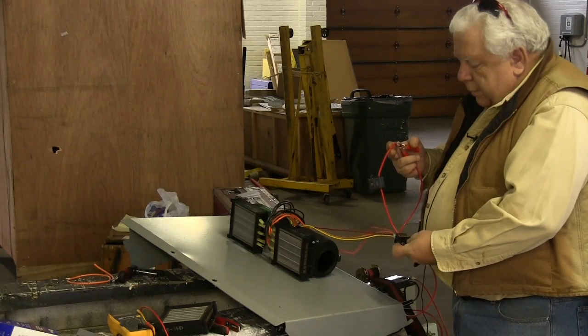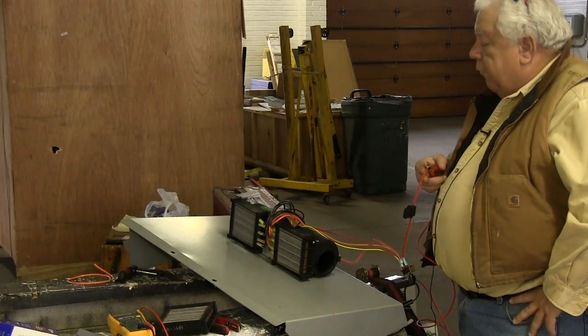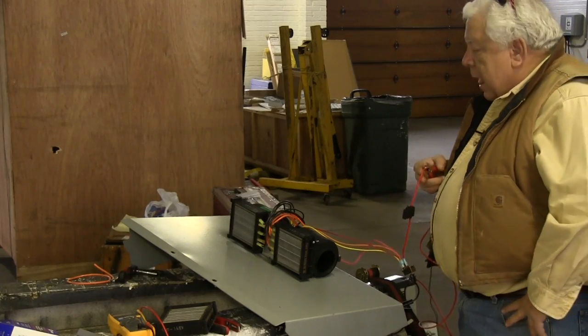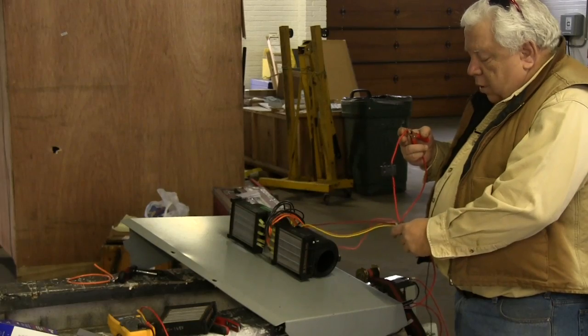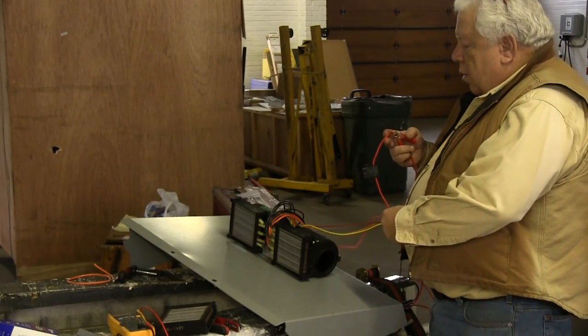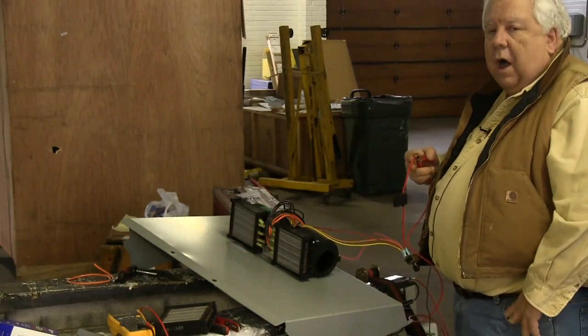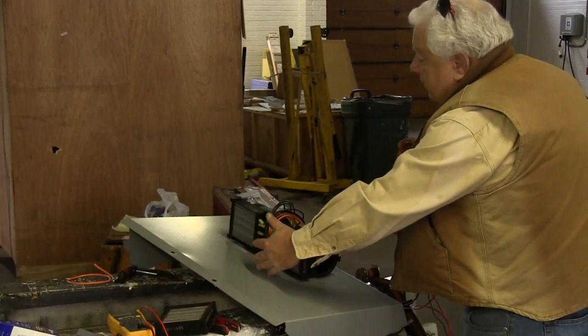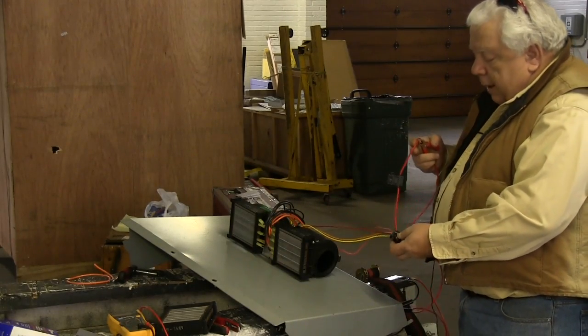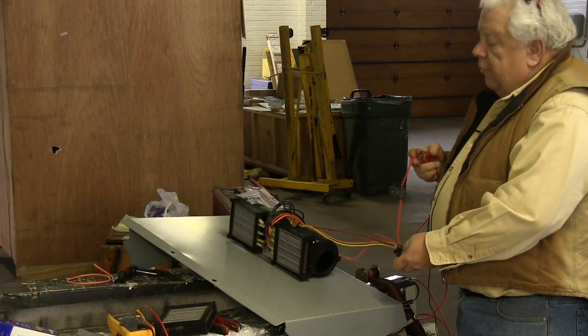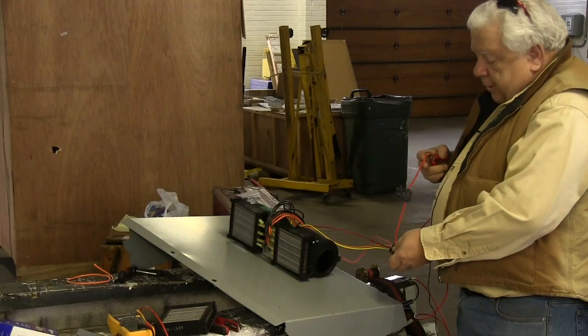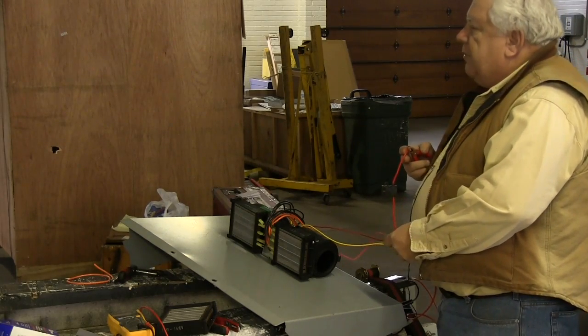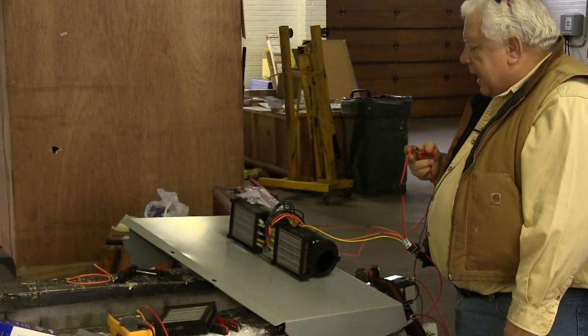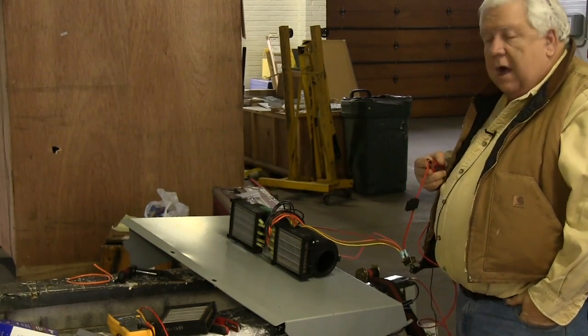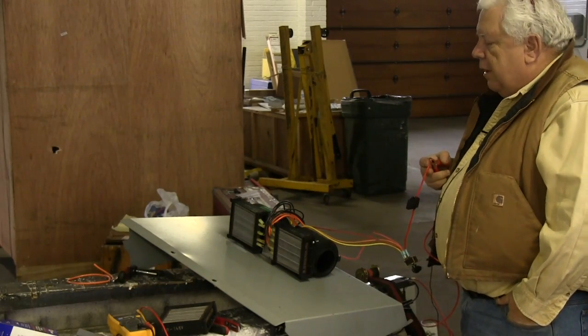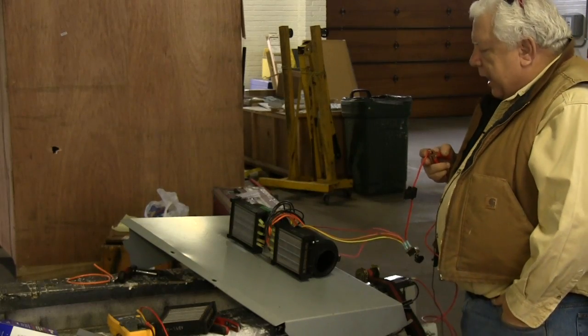If I go to medium, I get enough voltage through the coils of the fan to energize the contactor and turn on the heaters. And of course on high, I'm actually tied with a contactor to the high terminal, and so it'll do it. So this actually puts out quite a gale on high. As I turn it down, there's medium, I still have heat. When I turn it to low, the contactor remains engaged. And that's because it takes a lot more current to engage the contactor, about 1.3 amps, than it does to maintain the contactor, which is a couple hundred milliamps.